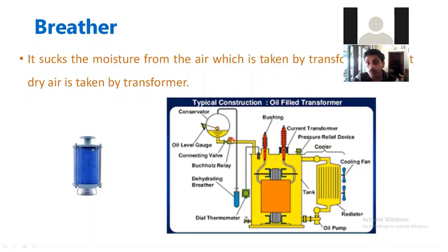There is a connecting pipe. There will be a Buchholz relay, which you can see in switchgear protection. Its purpose is that whenever there are internal faults, the relay sounds the alarm buzzer. That indicates there is some internal winding fault in the transformer. This is the breather, which is connected here. When the oil expands like this, if any moisture is there, the silica gel will absorb it, so that any moisture entering the oil will be removed. There will be a cooling fan. You can see ducts like this in a transformer. They are fins, for cooling purposes. There is a radiator and there is an oil pump. You can remove the oil.